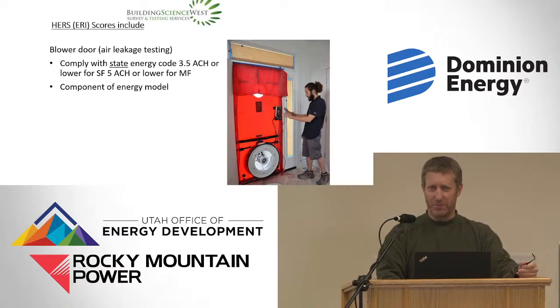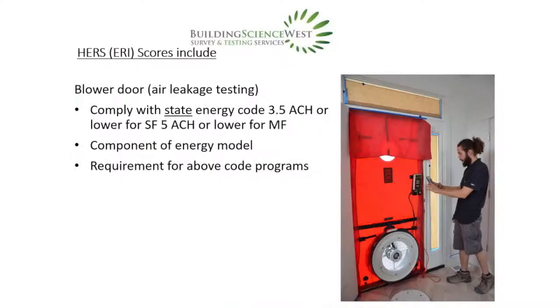I don't even know that our equipment would go up to this, but I know a gentleman who does air sealing, and he was working on units that were leaking 22 air changes per hour. Yeah, I'd probably have to put 2 fans in the door to get enough pressure to do that. If you're leaking 22 air changes per hour, you've got serious problems, and I would be afraid for the comfort of the occupants and the durability of the home at that point. Blower door testing is also required for above code programs. Energy Star requires it. Others as well, but again, typically Energy Star is a foundation for a lot of other programs.